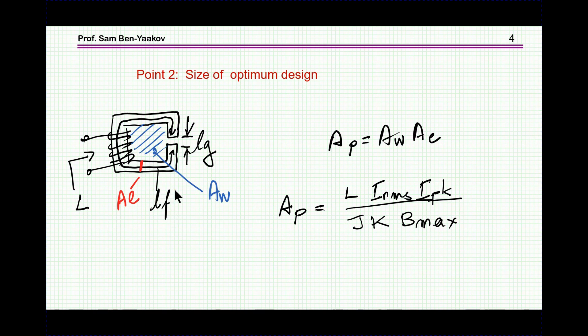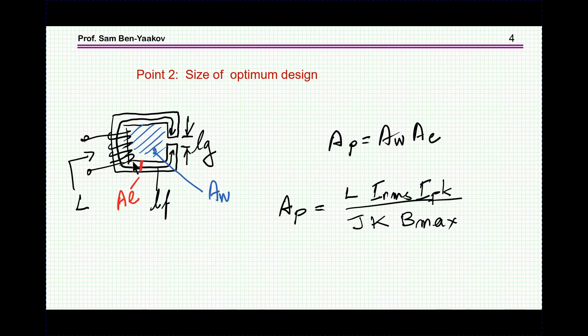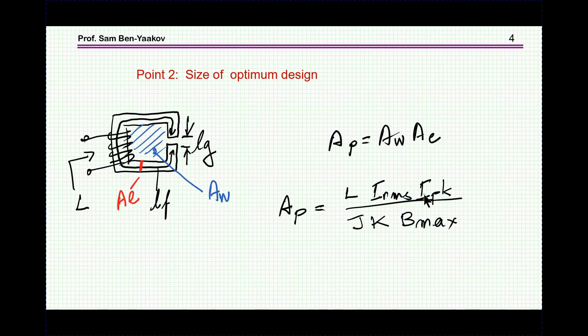Now let me start with the size. It can be shown very easily that the optimum size in terms of A_w times A_e — that is, the area product: winding window area times cross-section area of the core — is equal to this expression. This will ensure that we are filling up the winding window to the maximum. For a given B_max or delta B, J is the current density of the wires we are using, and K is the filling factor. So this will be the optimum size for these parameters, and it can be expressed as a function of B for the losses.